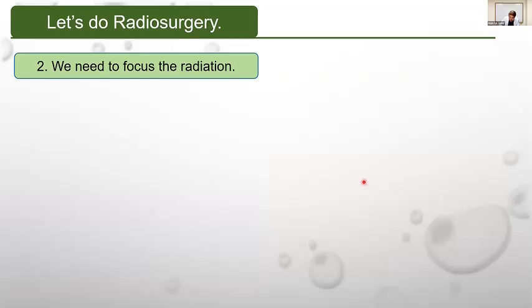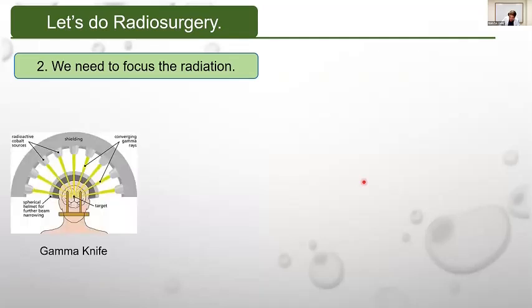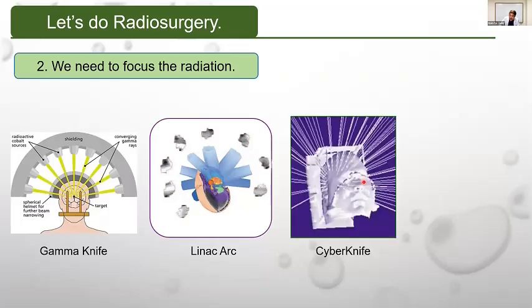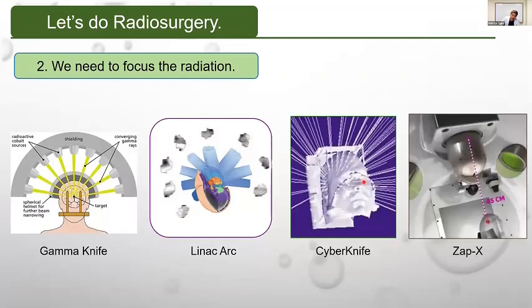Once we know where the tumor is, it's time to focus radiation on it. There are several ways to focus radiation, and this is what distinguishes each radiosurgery machine. The leftmost figure shows the principle of GammaKnife. The cobalt-60 sources are distributed around the patient head, and all the beams are adjusted to meet at the focus. Each beam is weak enough not to harm the normal brain on the path, but when the beams meet at the same point, the intensity becomes 200 times higher, and we can treat the tumor. Other experts will explain Linac, CyberKnife, and ZAP-X later.